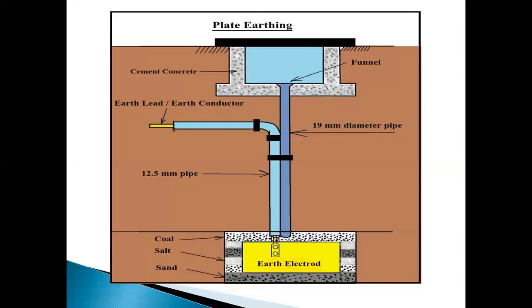A galvanized iron pipe of 12.5 millimeter diameter is connected to the plate by means of bolt, nuts, and washer for carrying the galvanized iron wire for connections to the earth plate. Another pipe of 19 mm diameter is connected to the plate for carrying water. So from this plate arrangement, we are going to use two pipes. One is the 12.5 mm pipe, used for connections to the earth plate. The other is the 19 mm diameter pipe, which is connected to the plate for carrying water and is connected to the funnel with the wire mesh to pour water.